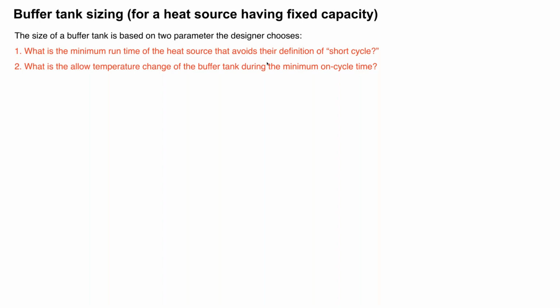Now, when it comes to sizing a buffer tank, there are a couple of things we want to do. What is the minimum runtime that we want that heat source to operate with, where it is not short cycling? And there's no formal definition of a short cycle. If you asked people in the trade whether it's a short cycle if their heat source turns on, runs for 1 minute and then shuts off, most of them would say yes, and I certainly would agree. At 5 minutes, probably a few less would say that's a short cycle. I like 10 minutes as a reasonable number.